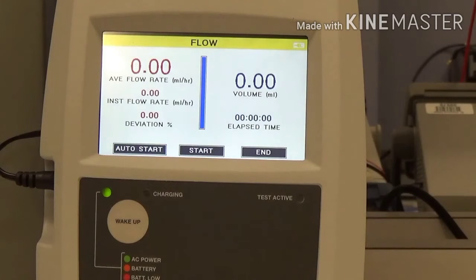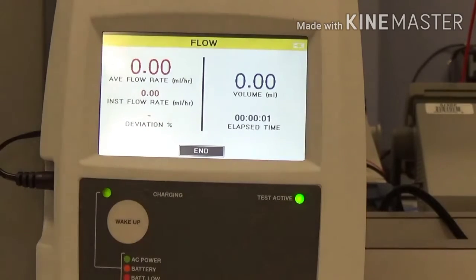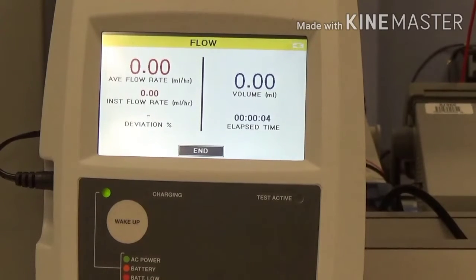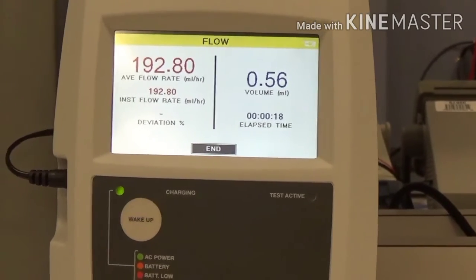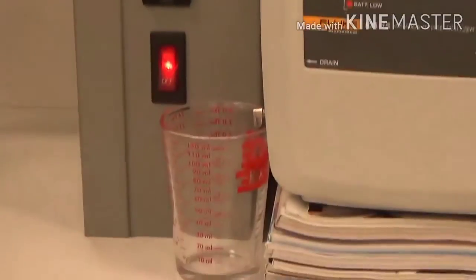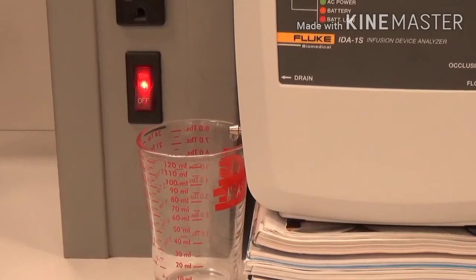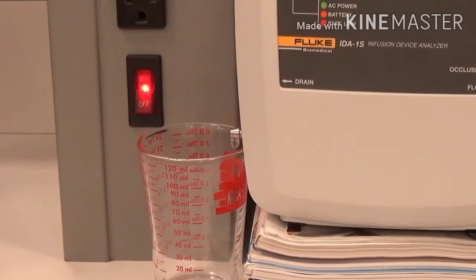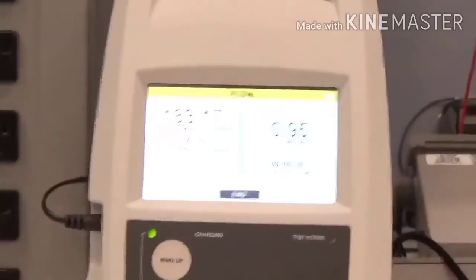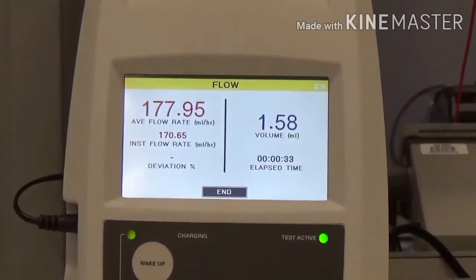So at this point, all we need to do now, I'm going to start my infusion device and I'm going to start the test at the same time. Start and start. We should see some numbers coming up shortly. There they are. That lets us know the device is currently functioning properly. And another thing we can do, we can actually test our theory here. You can see the water dripping into our beaker. So this should take about 10 minutes. I'll come back here in just a few minutes and see where we're at.